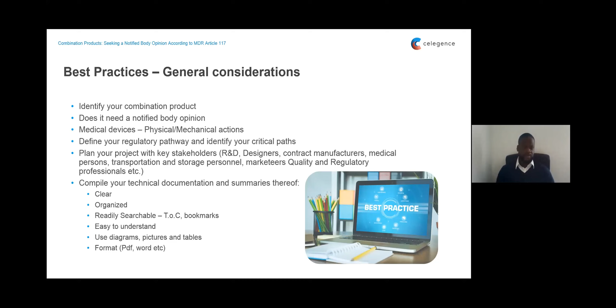Make sure you compile your technical documentation and any summaries of it that are needed. The MDR makes it clear that your technical documentation must be clear, organized, and readily searchable. So use bookmarks and a table of contents where needed, and use formats that are acceptable, depending on the notified body and what formats they will accept. It could be a PDF, it could be a Word document. Find out from your notified body how they want it submitted, and make sure you use diagrams, pictures, and tables. Make it easy to be understood. Your technical documentation must be easily understood by your notified body.